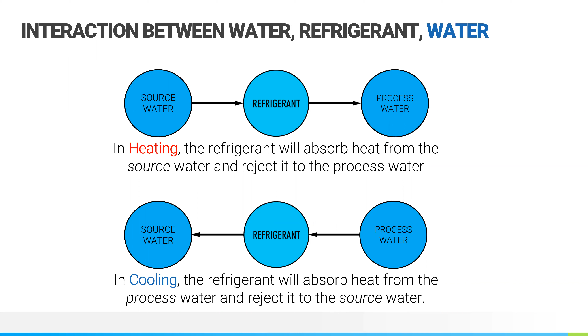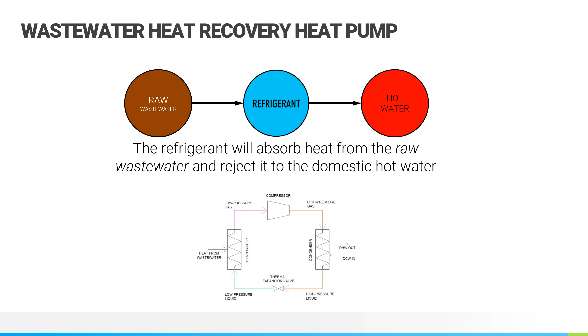So, circling back to wastewater heat recovery. What we'd see on a wastewater heat recovery heat pump is raw wastewater transferring to a refrigerant loop, transferring to a hot water loop. The refrigerant absorbs heat from the raw wastewater, and then that heat gets rejected to another coil that creates the domestic hot water for your building. That's how we're able to close that endless loop of just dumping energy down the drain on a building-by-building basis, and capture that energy from the wastewater and transfer it into an all-electric and super highly efficient domestic hot water source. It's a good little reminder: flushing our energy down the tubes. Yep, quite literally.